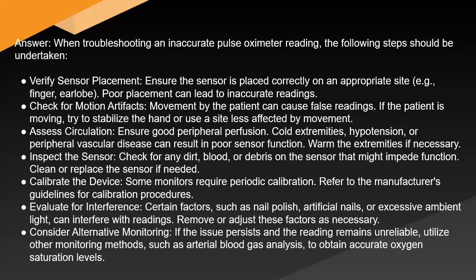Assess circulation. Ensure good peripheral perfusion. Cold extremities, hypotension, or peripheral vascular disease can result in poor sensor function. Warm the extremities if necessary. Inspect the sensor. Check for any dirt, blood, or debris on the sensor that might impede function. Clean or replace the sensor if needed. Calibrate the device. Some monitors require periodic calibration. Refer to the manufacturer's guidelines for calibration procedures.